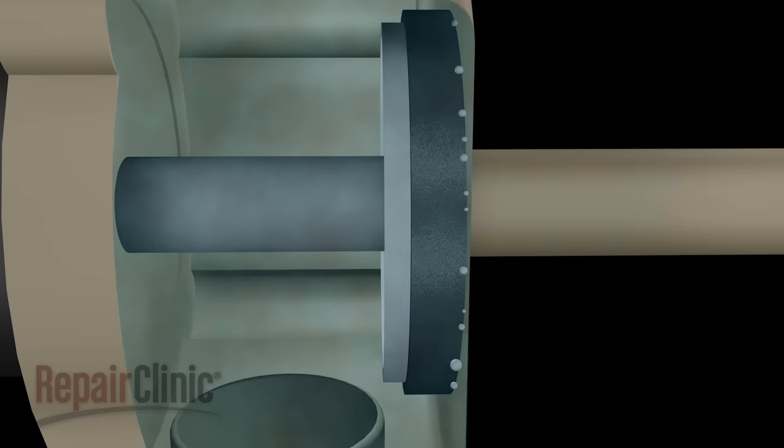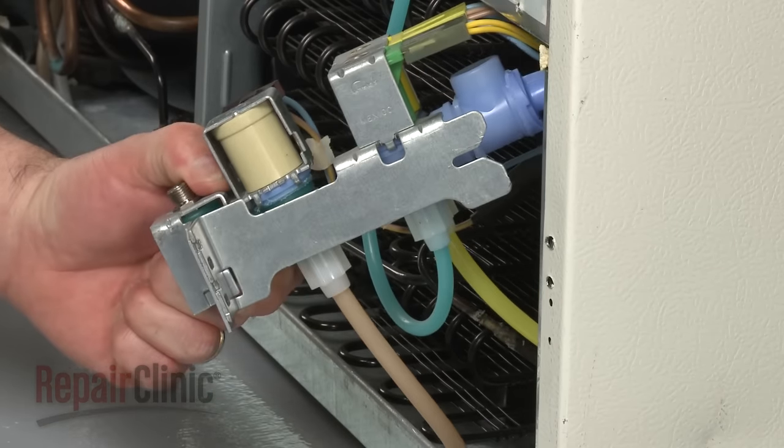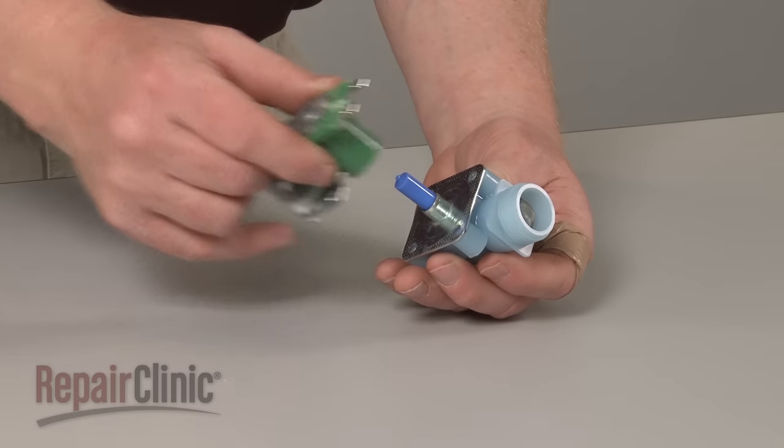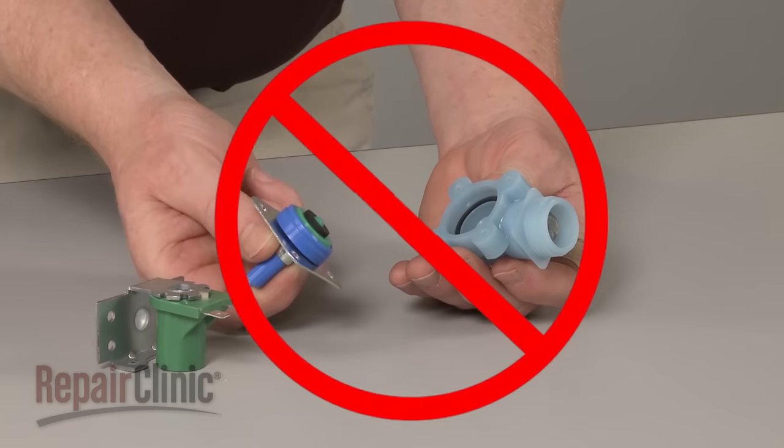Mineral deposits can build up in the valve, creating a restriction that causes the noise. A restricted valve should be replaced. Trying to clean out an old valve is not recommended, due to the risk of part failure after repair.